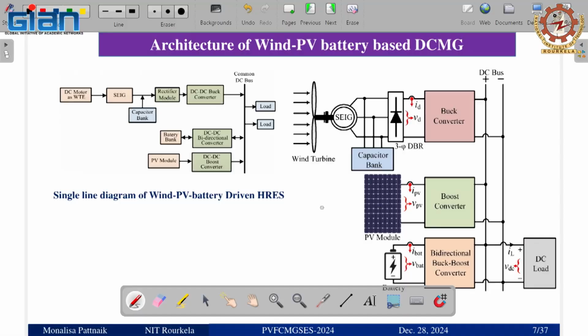we have to stop it. So for the wind power, we have different modes of operation, the range of operation, you can say, between the cut-in and the cut-out, and the rated speed. Okay, so between the cut-in and rated, you have the MPP zone of operation, and then you have to limit the power, and after cut-out you have to stop it. Okay, so this is the protection zone of the wind energy conversion system, and this is the MPP zone. Okay, and then you have to stall the machine, means you have to stop it.